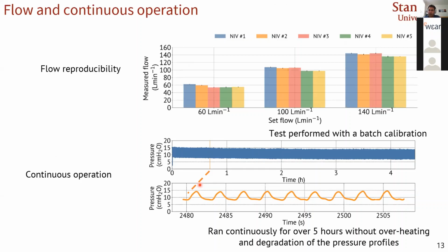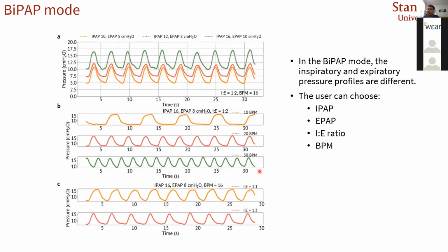It's just I had to shut it down because it was getting late at night. And we were getting good pressure profile throughout this whole 5 hours of testing. Then here I'm showing the BiPAP mode. In CPAP mode, that's the continuous positive air pressure, you will have one flat line pressure. In BiPAP mode, what happens is you have 2 different profiles in the inspiratory and the expiratory.